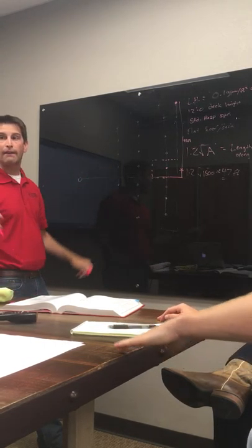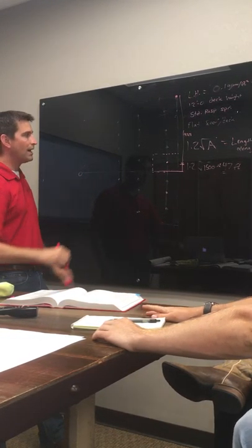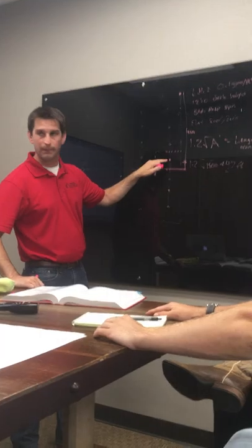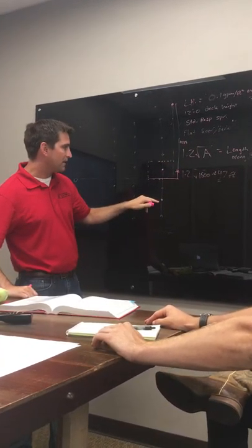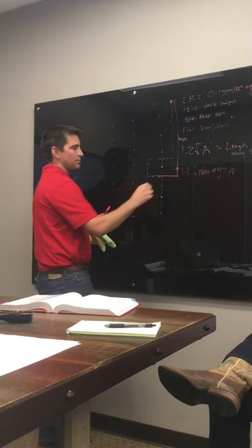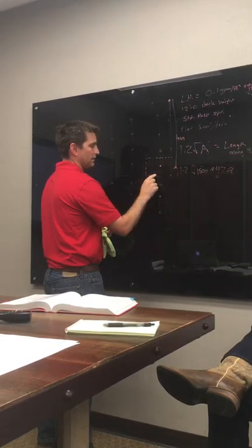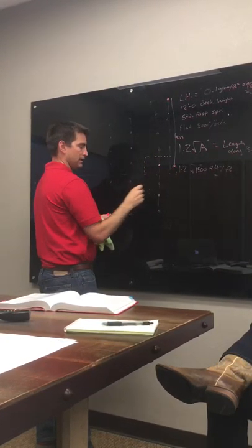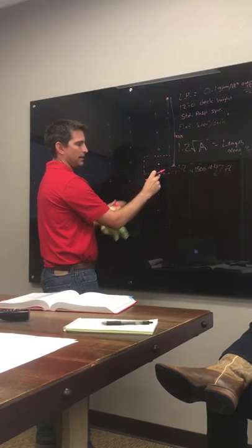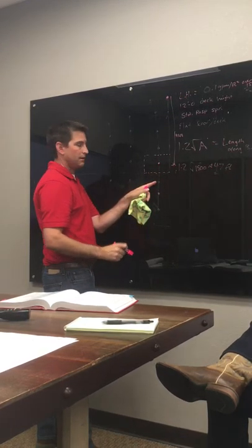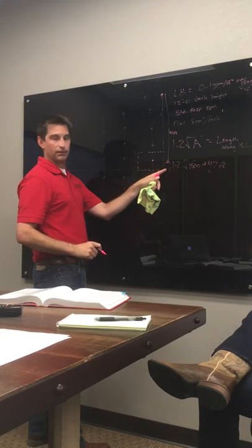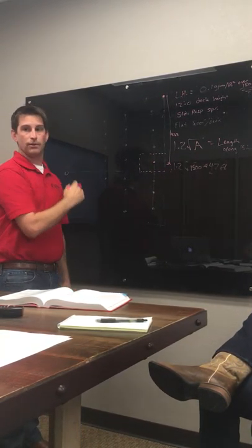I don't wanna go any further than I have to, because if I go longer than I really have to, I will be 47, so if I do that, I may be a 50. But I have to go at least 47 and pick up that head. I don't want to go 60 feet, because now I'm just killing myself. Why did you go a little bit farther? So this sprinkler is protecting halfway to there, and this one sprays back halfway to there. Same thing here, it sprays halfway and it sprays halfway. So you just want to get the full coverage area. Where you break your remote area is to the edge of where your sprinkler is protected to.